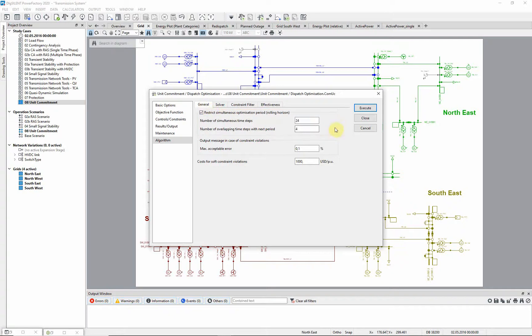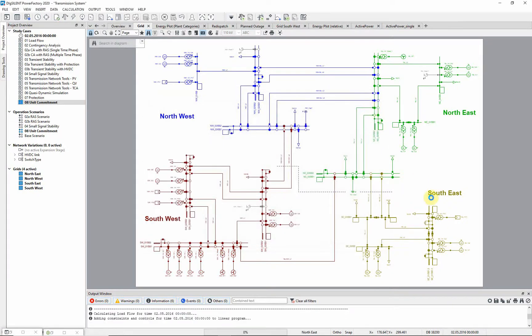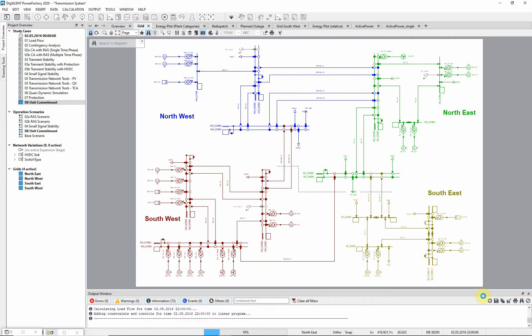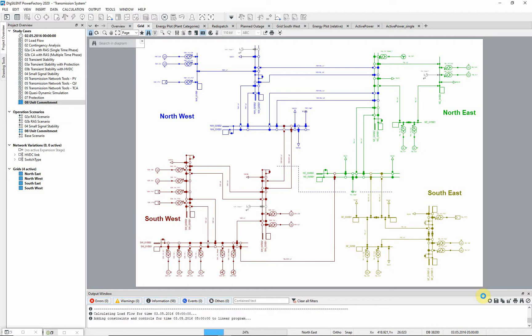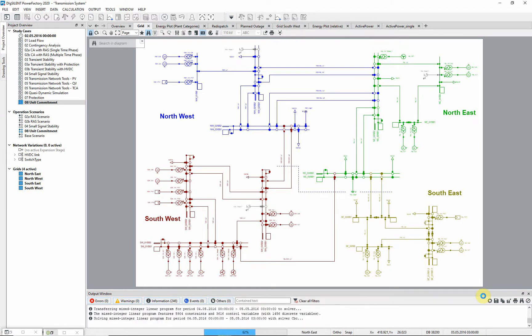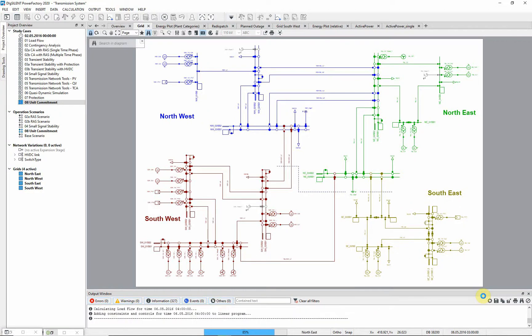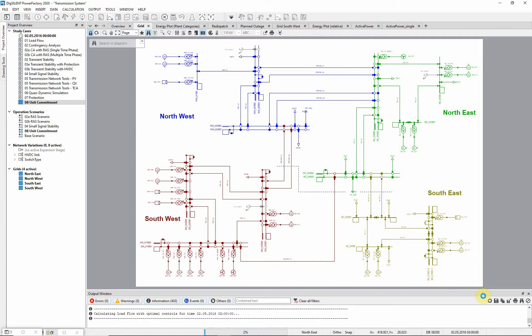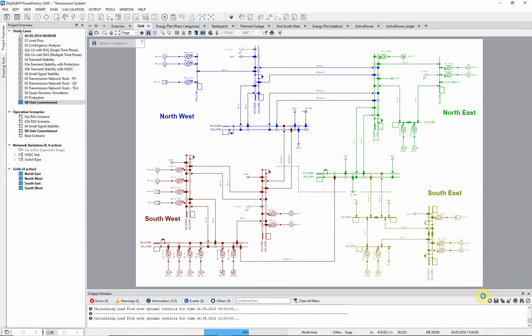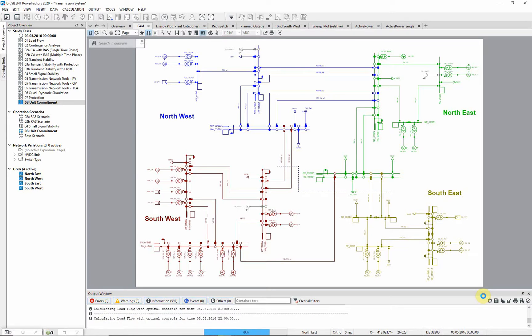We will now execute the unit commitment simulation. In order to execute unit commitment and dispatch optimization in PowerFactory, it is necessary to have a converging load flow in every time step of a quasi-dynamic simulation in the defined time period, because the load flow results of each time step are used for the initialization and linearization of the mixed linear integer problem that is solved in the unit commitment.